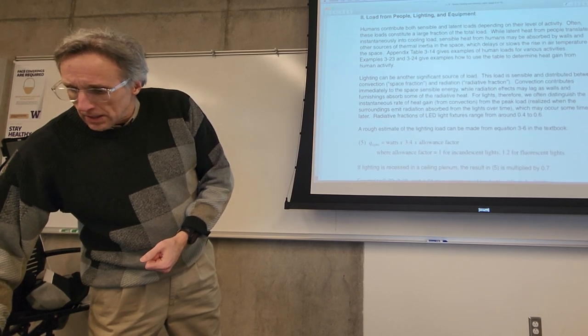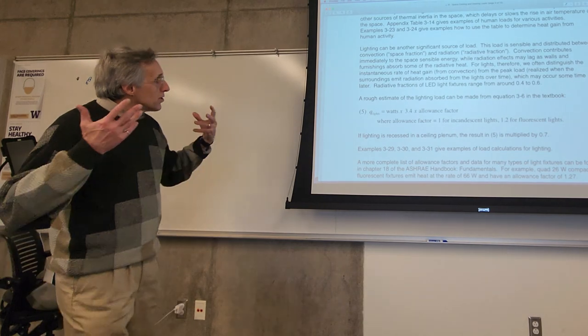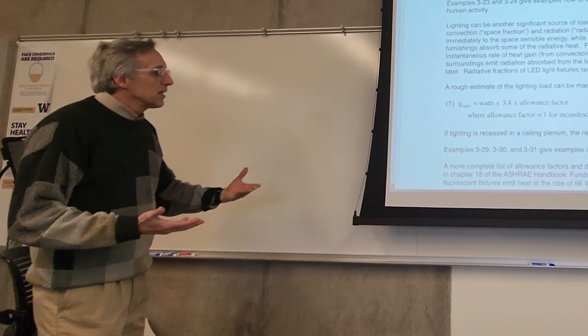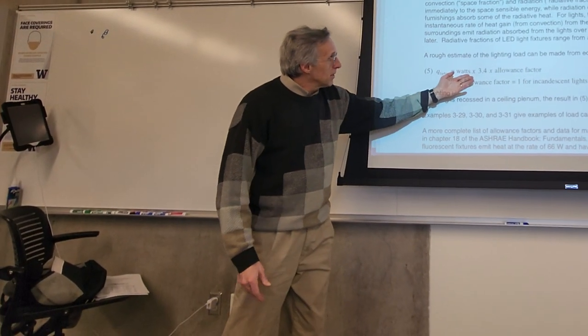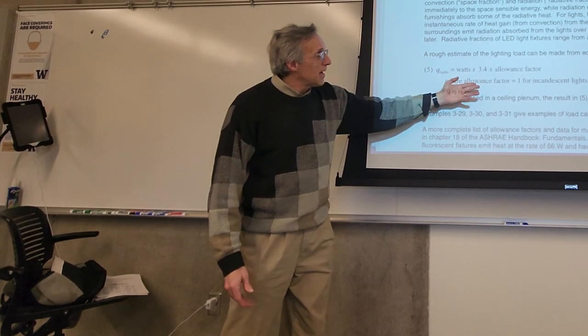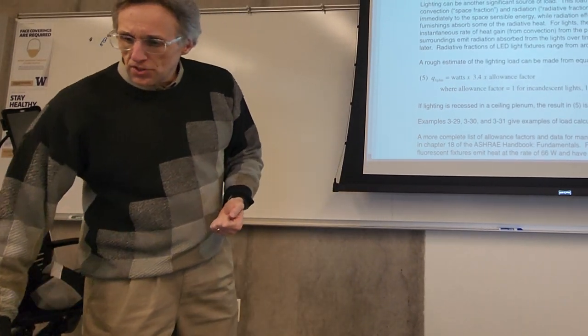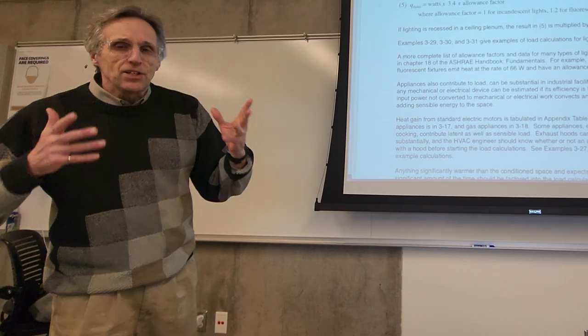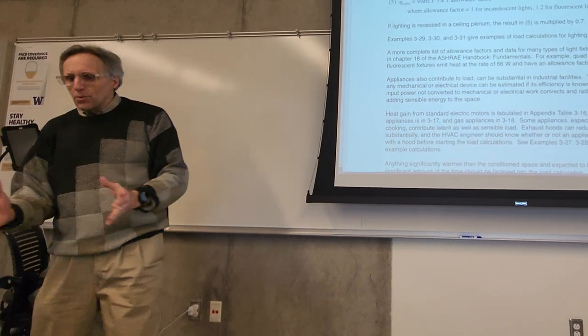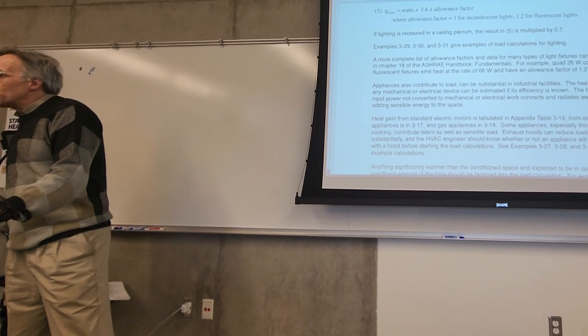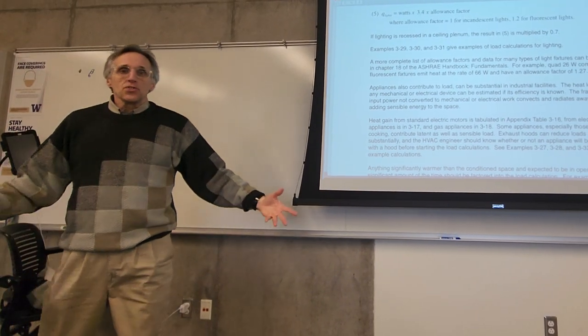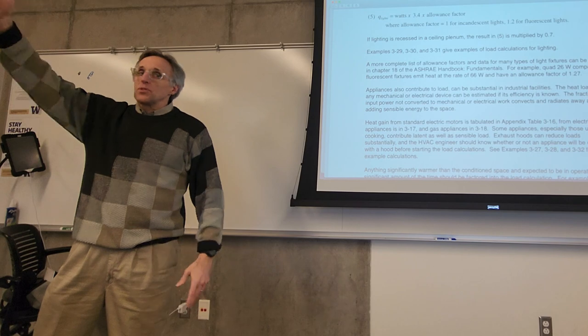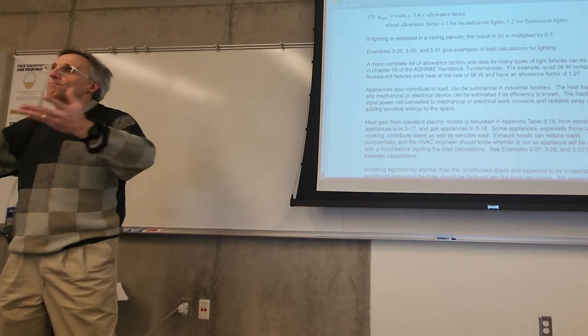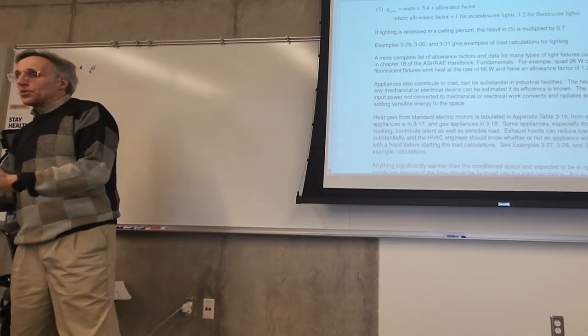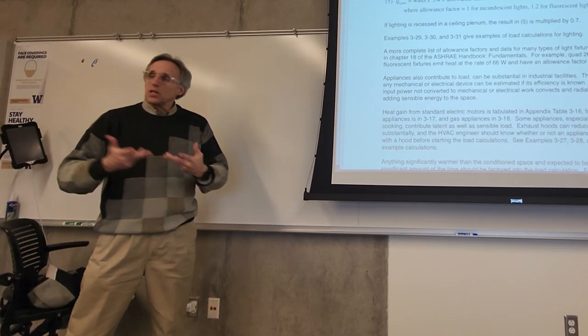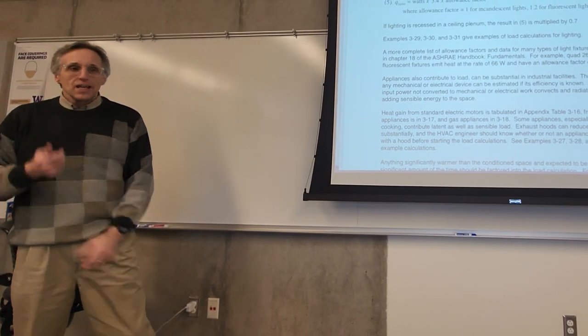Ventilation. Okay, load from people. There's a technique we have to use to take into consideration the heat generated by lights, and there's a formula for that and data, and that's in the chapter for today. A lot of that you just have to glance through. There's a lot of tables: how much heat does a computer monitor put into the space, and how do I factor that in? So a lot of today's reading is just tables and equations for using that data to calculate the heat load on the space.